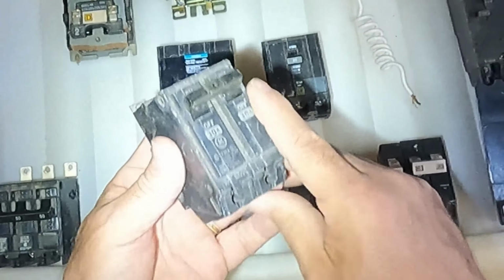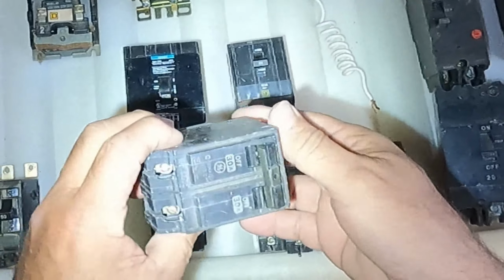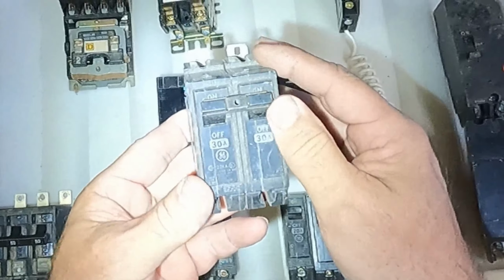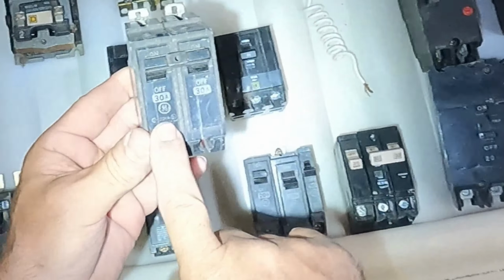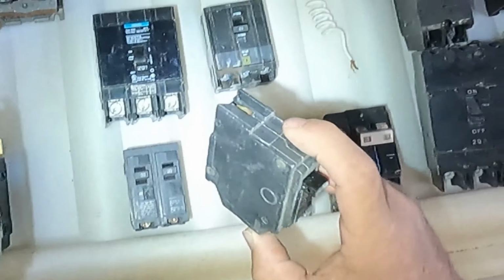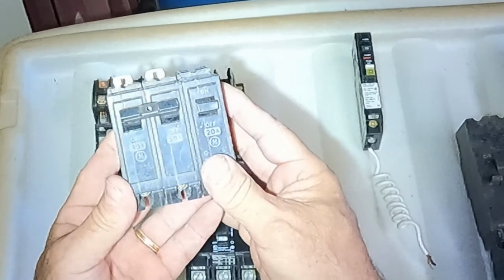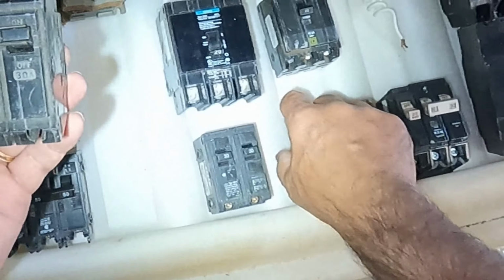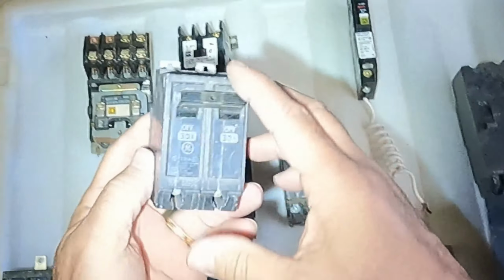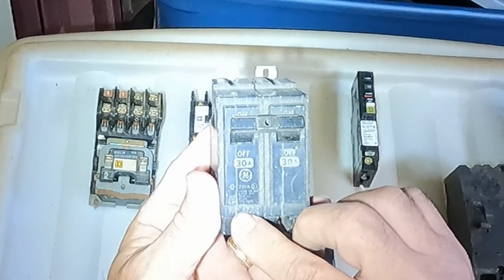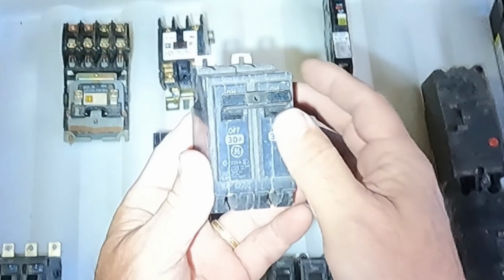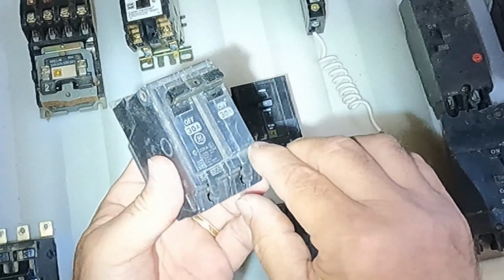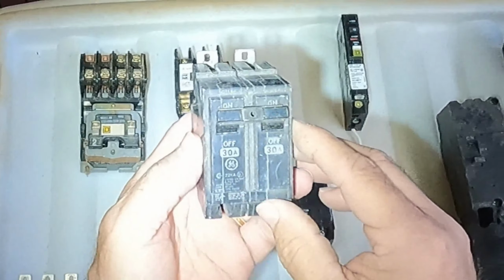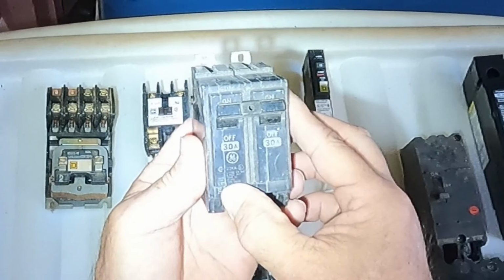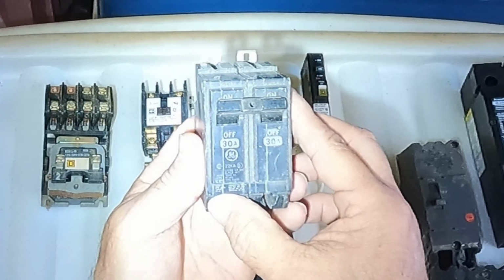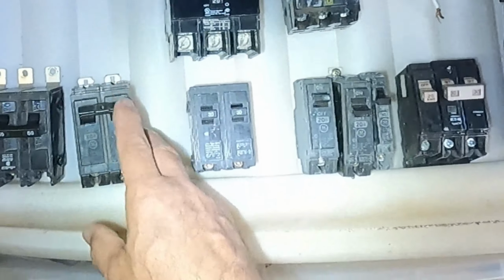Here we have a GE 30 amp 2-pole breaker, again, a higher KAIC rating because it's a bolt-on. And this is rated at 22,000 KAIC, where a standard residential breaker like this is rated at 10,000 KAIC. That's the max interrupting current that this will protect you from. Arc flash. And this is not rated for DC. If it doesn't clearly show a DC signal, you know, that straight line with the dotted line underneath it, it is not rated for DC. It's not listed. So there's a 2-pole. Sorry, it's really small lettering. This is not rated for DC.